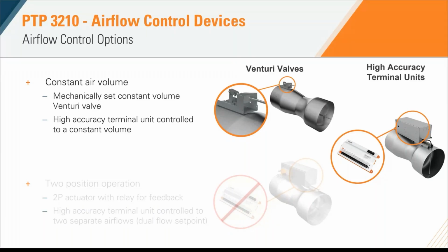Now, if we wanted to design a high accuracy terminal unit to operate in a constant volume application, we will still have to have some sort of controller or actuator since we need those electronic components to give us that pressure independence.